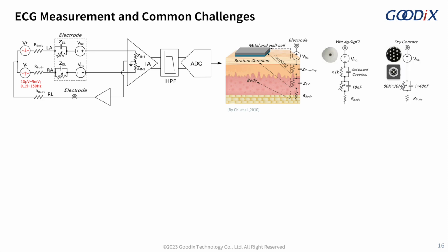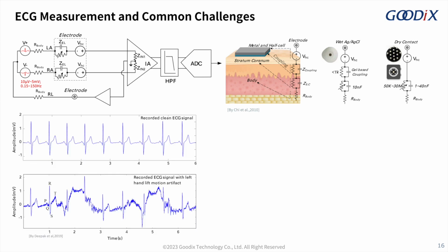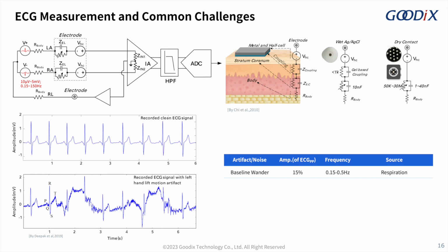The wet electrode is applied with conductive gel and can reduce the contact impedance with the skin, while the dry electrode is in direct contact, and the contact impedance fluctuates greatly. All of this makes the real ECG signal noisy compared to the ideal signal. The noise comes from baseline drift. It's caused by changes in respiratory impedance and is about 15% of the ECG amplitude. It's mainly below 0.5 Hz.